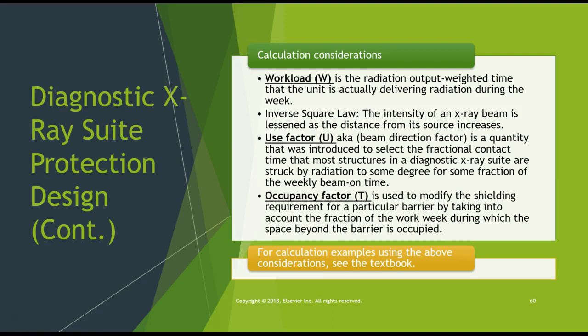Okay. Inverse square law, of course, applies. The use factor is also known as the beam direction factor. You need to remember that. That's a test question. And it's the quantity that was introduced to select the contact time that most structures in that suite are going to be struck by radiation. Okay. And then the occupancy factor is used to modify the shielding requirement for a particular barrier, either primary or secondary, by taking into account who's going to be in there during that work week.